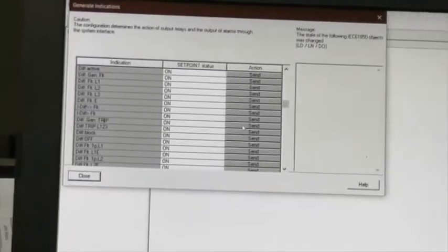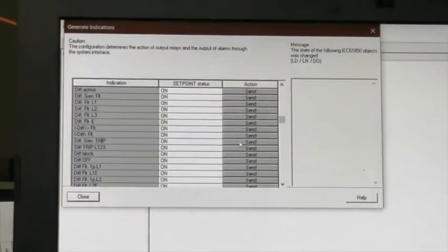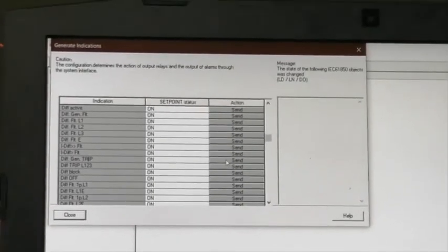So let's check the signal. How are we going to check the signal? We will force these protection functions from the 11 kV protect relay, because these protection functions are only in the 11 kV protect relay. So we will be using the relay software, protect relay software, which is DigSi 4, to force the differential and REF protection. So we will proceed one by one. First we'll do differential. Let's check the normal condition now.